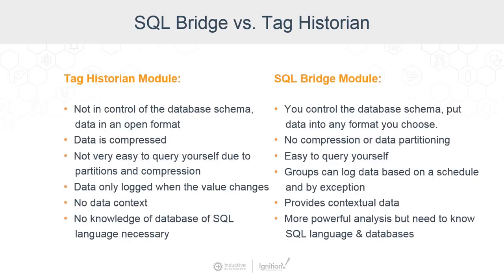Putting them side by side and doing some comparisons — pros and cons. On the Tag Historian, you're not in control of the database schema. The data is in an open format in the SQL database, but we control the schema and we do data partitioning, separating data into separate tables in the database to maximize performance. Ignition takes care of that so customers don't have to worry about knowing much about databases. We log data as it changes, use algorithms for some compression so we don't log data unless we actually need to, and we do interpolation when bringing that data back. There's really no knowledge of SQL language necessary.